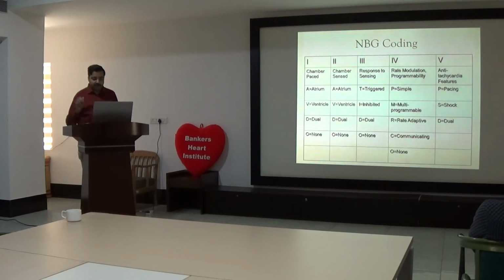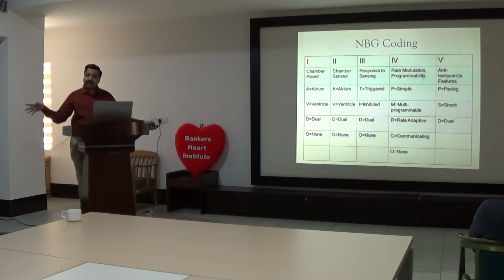Then there are the fancier and newer parameters. P is simple, not used. M is multi-programmable. R is rate adaptive, which is very commonly used. Why is rate adaptive required? Suppose your patient's heart rate requirement is around 80 and you set the pacemaker at 80. Once that patient starts walking or running, the demand of the body will increase, so the heart rate has to go from 80 to 100. How will it be sensed? The pacemaker senses it with change in body movement and change in the QT interval, and it senses that the patient is exercising and requires more heart rate. The pacemaker rate will automatically increase from 80 to 90 or 100, whatever is required. That is rate responsiveness or rate adaptiveness, a common function used now.